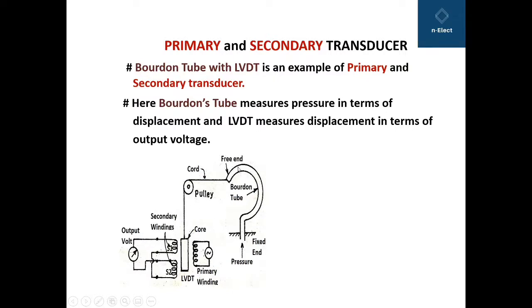What does the LVDT do? The displacement of the Bourdon tube, through the cord, moves the core upward. When this core moves up, the number of flux linkages from the primary to secondary S1 and from the primary to secondary S2 will change. Therefore, the voltages across S1 and S2 will differ, and since S1 and S2 are connected in series opposition, the difference of these two voltages appears as a differential output voltage.